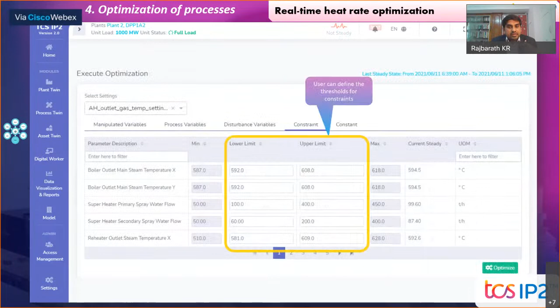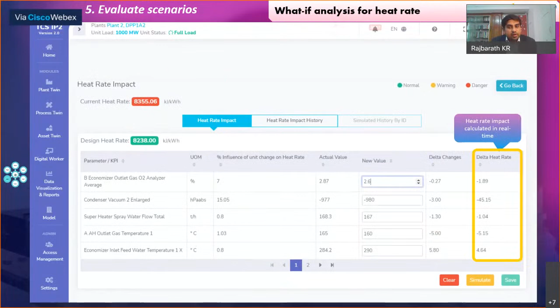Next one is on evaluating the scenarios. So on evaluating the scenarios, what we see is that for you to operate the plant at different loading conditions, different kinds of coal, the operators can themselves create the scenario. They can key in the values for the set points which they want to do and simulate what will be the impact on the heat rate. So this is the simulated impact on heat rate, and if it is good, they can go ahead with setting it in the plant.